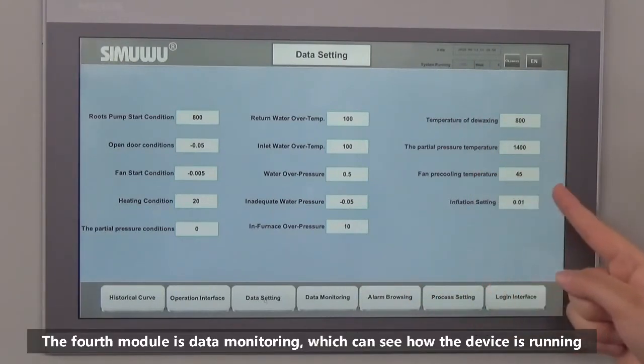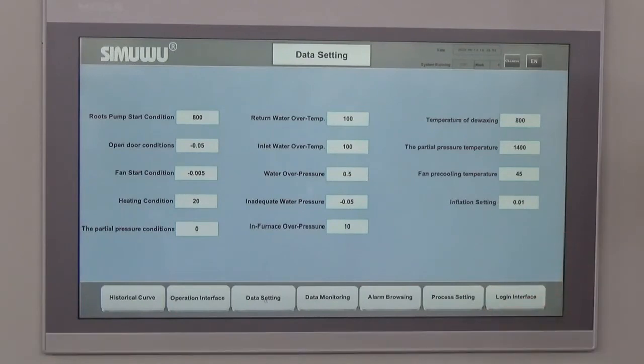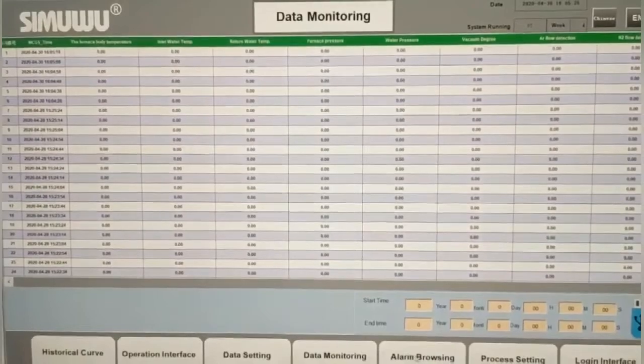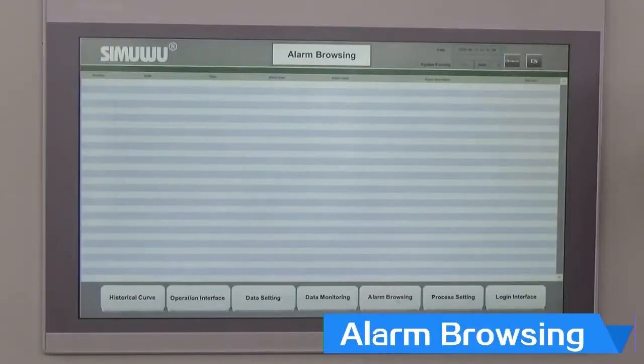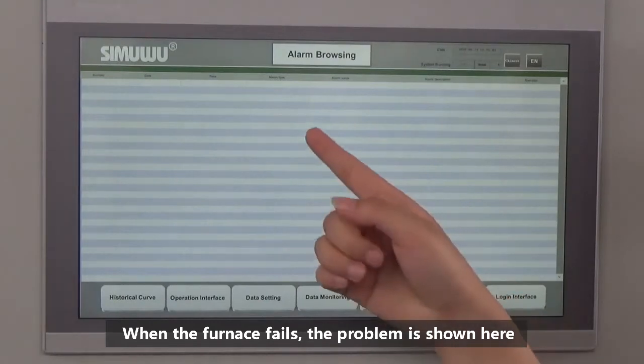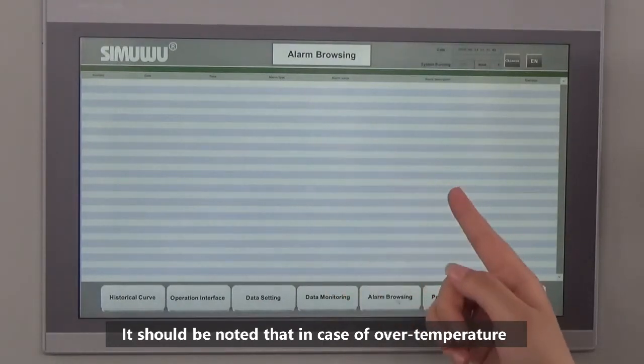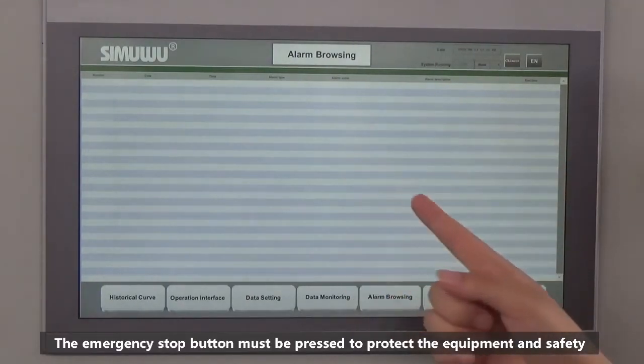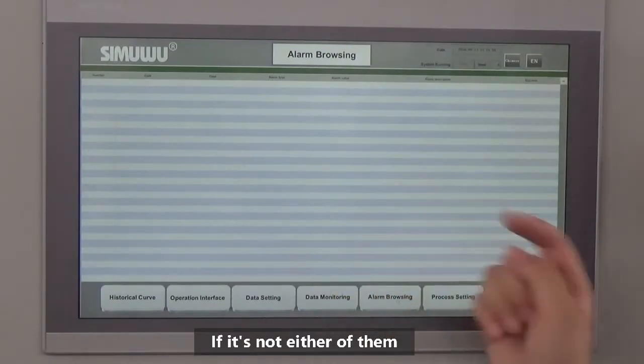The fourth module is data monitoring, which lets you see how the device is running. The fifth module is alarm browsing — when the furnace fails, the problem is shown here. It should be noted that in case of over-temperature or over-pressure, the emergency stop button must be pressed to protect the equipment and ensure safety.